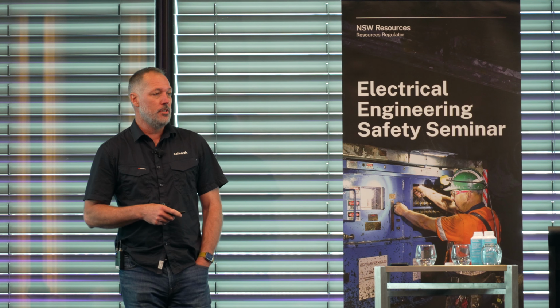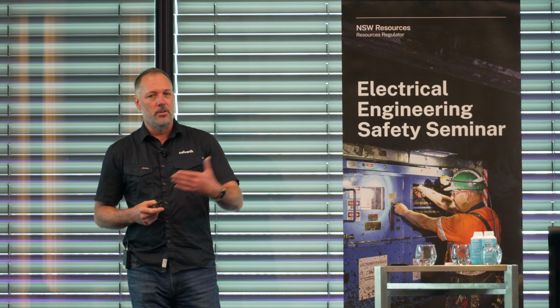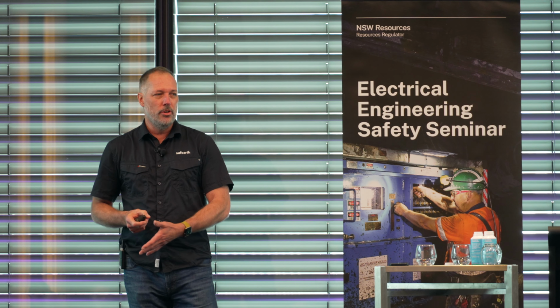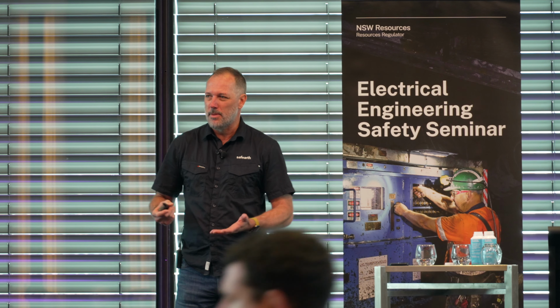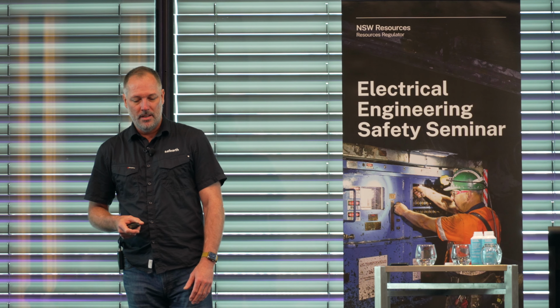Separation can assist with lightning risk. If the line receives lightning strikes and there's a separation somewhere, if it's built and designed well, you won't see those transient voltages on your earthing system or at the mine. That may be an advantage. It can work both ways.